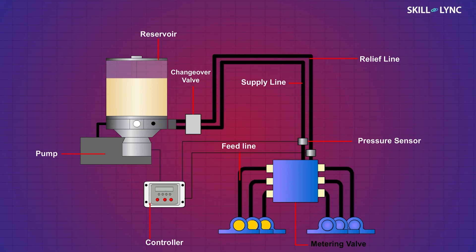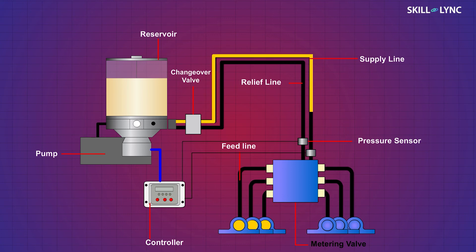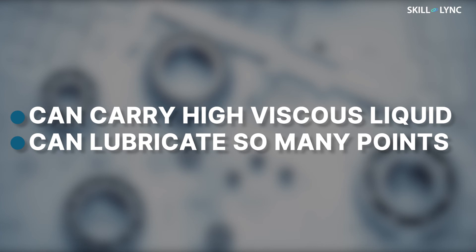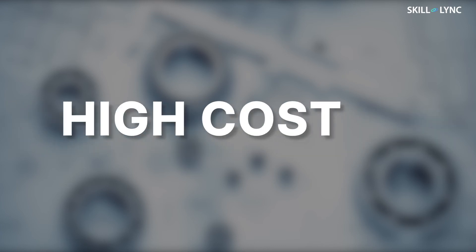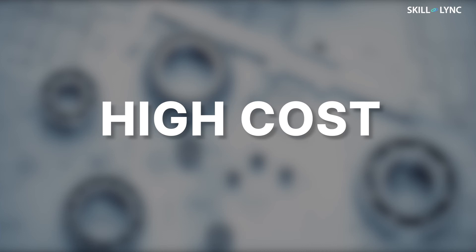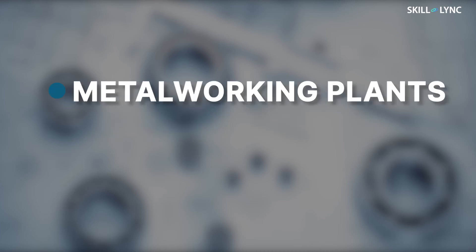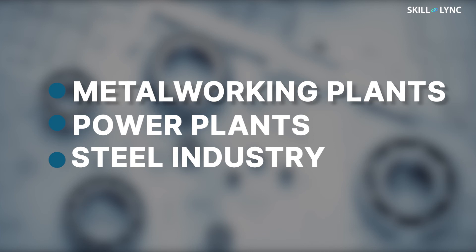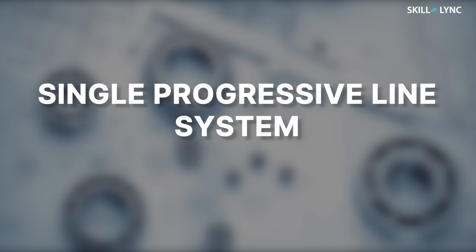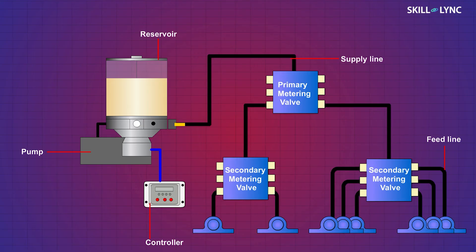After sufficient pressure is attained in the supply line, the controller shuts off the pump and sends a signal to the changeover valve, which switches the supply. The next time the controller switches on the pump, the lubricant enters through the second line and now the first line acts as a vent. The remaining points get lubricated, and this cycle continues. This system can carry high-viscous liquids and can lubricate many points, but the cost is comparatively high. It is used in metalworking plants, power plants, and the steel industry.